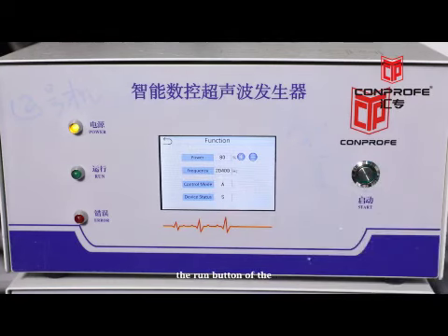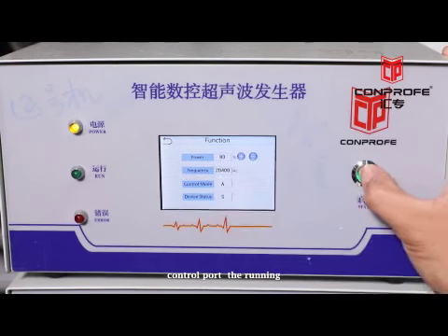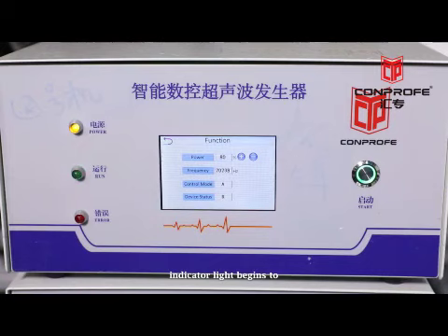After you press down the run button of the control port, the running indicator light begins to flicker and the generator begins to search for the transducer's resonant frequency. After the resonant frequency is found, the running indicator light becomes normally on and the generator starts to work at the resonant frequency. After you release the run button, the running indicator light goes out and the generator stops working.